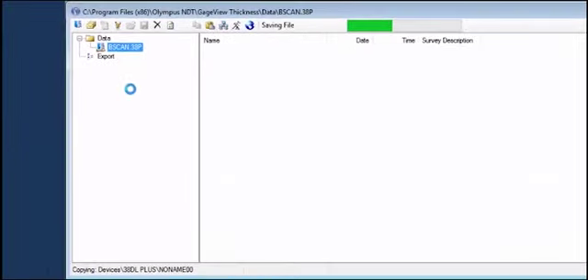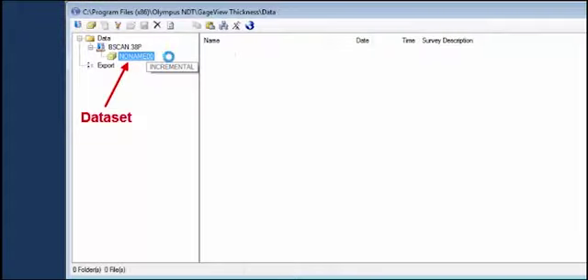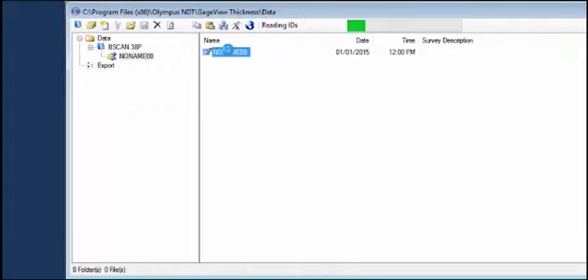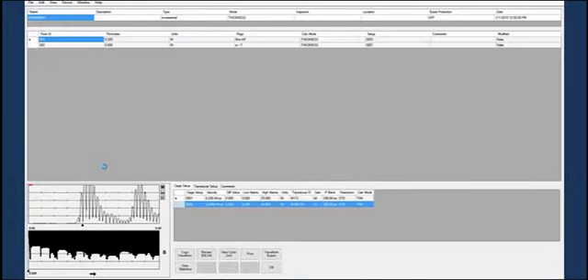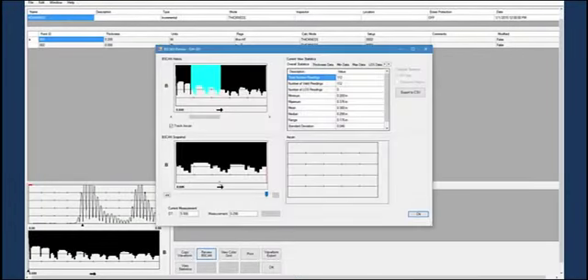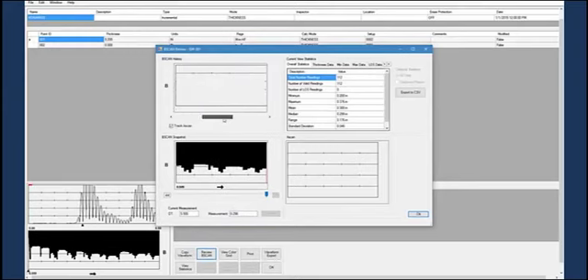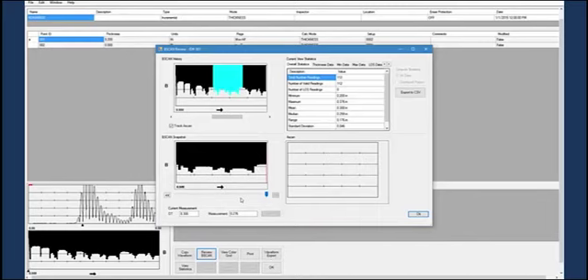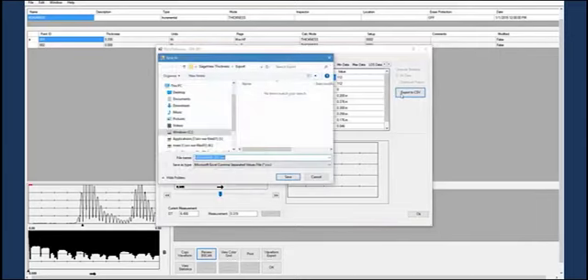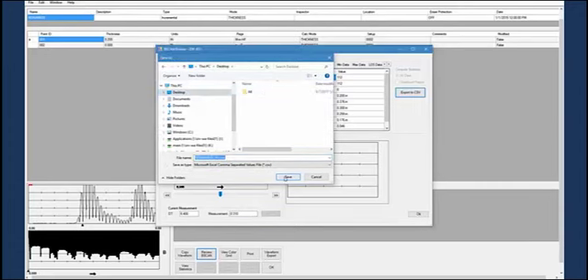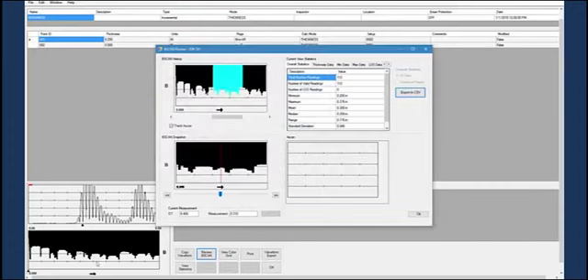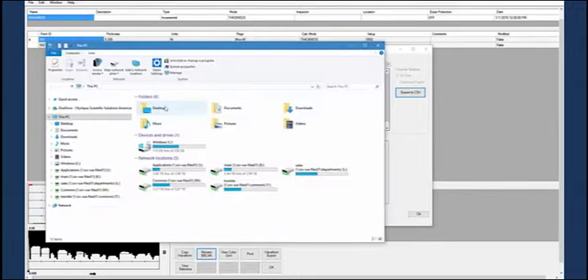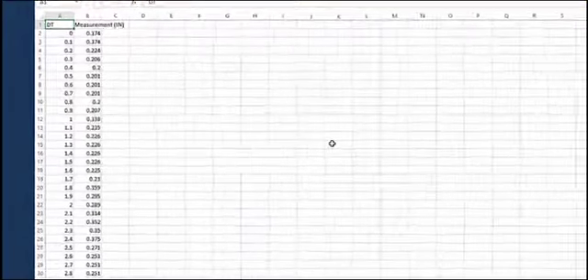You can now transfer the file into GageView Thickness. Once the file is transferred, you can click the dataset once and then double-click the survey file, which is the file name with the pencil and paper icon next to it. You can then click Review B-scan. The image on top shows the full encoded B-scan and allows you to highlight a certain portion of the scan to examine, while the image below displays the highlighted portion of the scan and allows the user to review the scan with the cursor. The user can also click Export to CSV. The user will then be prompted to choose the location on their computer to save the spreadsheet. Once saved, they can navigate to the file and open it. This will open a spreadsheet with all of the thickness readings and their corresponding distance traveled.